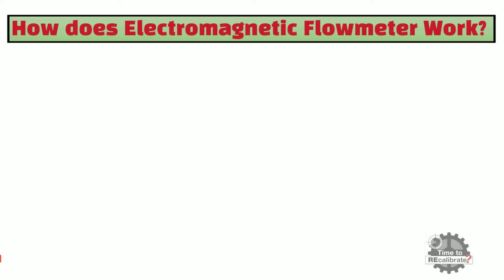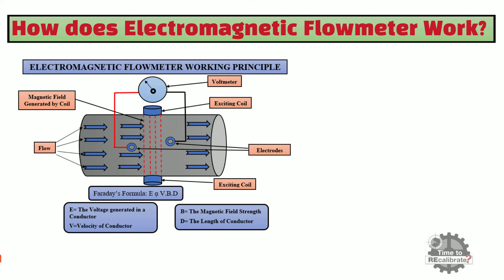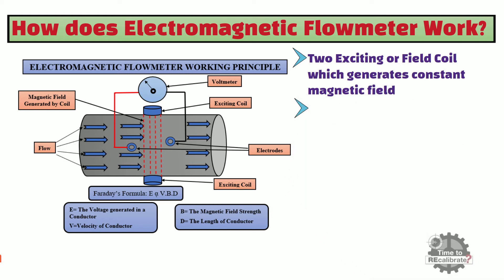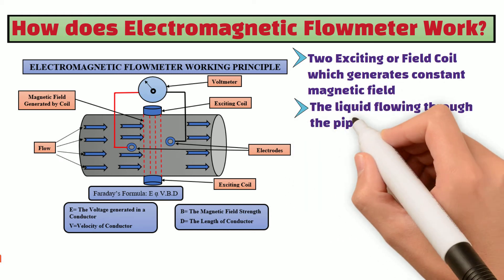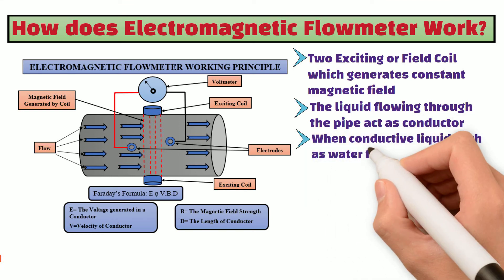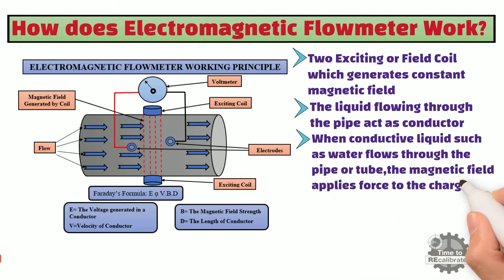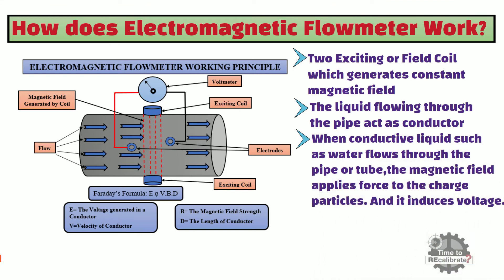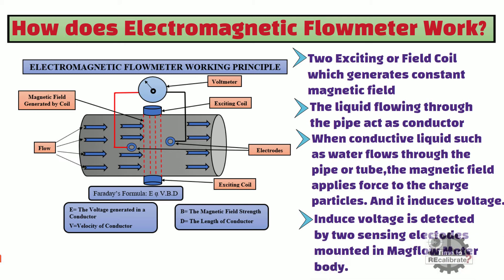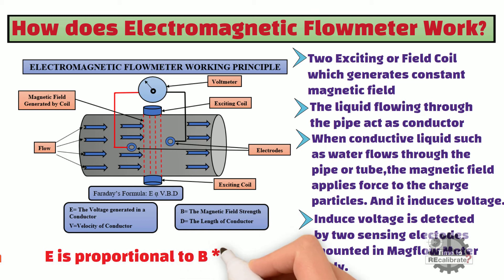Now, how does an electromagnetic flowmeter work? As you can see from the picture, the mag flowmeter has two exciting coils that generate a constant magnetic field. The liquid flowing through the pipe acts as a conductor. When conductive liquid such as water flows through the pipe, the magnetic field applies force to the charged particles and induces a voltage. This induced voltage is detected by two sensing electrodes mounted in the mag flowmeter body. The induced voltage E is proportional to B × V × L.